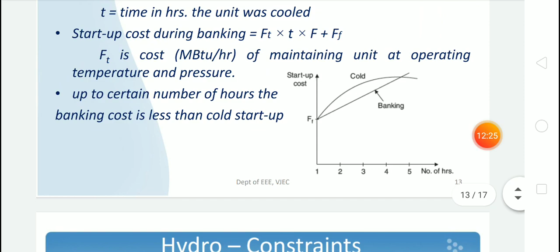So startup cost can be calculated as Fc into (1 minus e raised to minus t by alpha) into F plus Ff. That is for cold startup, where Fc is the cold start cost and F is the fuel cost, which is related to the power generation, F equal to some Fn and Pn square, like that. And Ff is the fixed cost, that is the salary of the operating personnel, maintenance expenses, etc. And alpha is the thermal time constant, and t is the time.